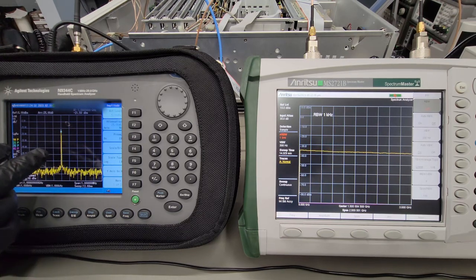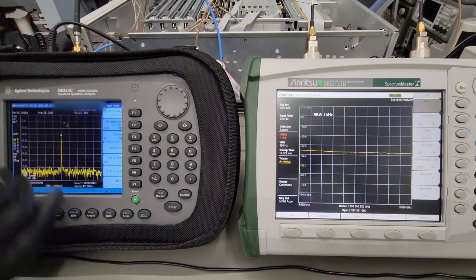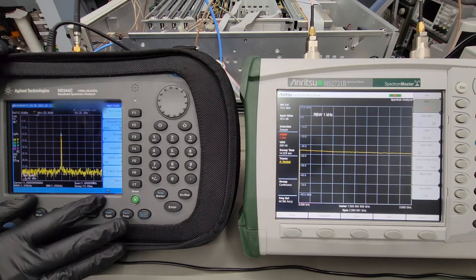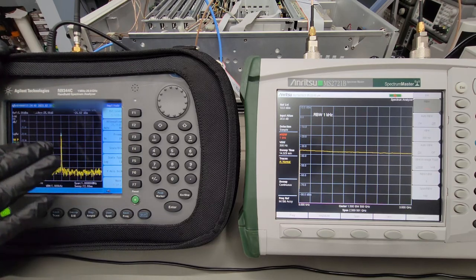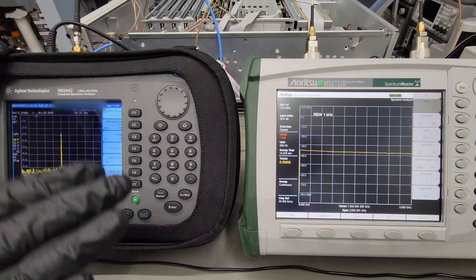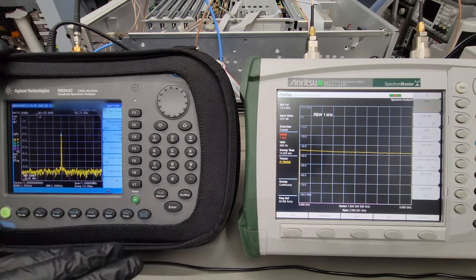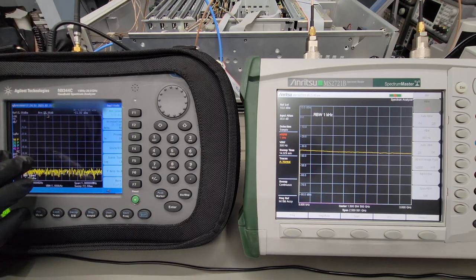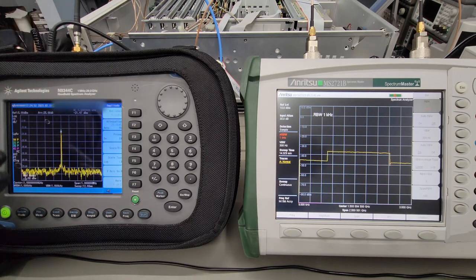And of course, you can see on the instrument here how it actually interpolates between the different attenuator steps. So the output from the microwave circuitry is only subdividing on, you know, small dB increments. And then once you switch in the next attenuator stage, the amplitude will actually shoot back up again over here.